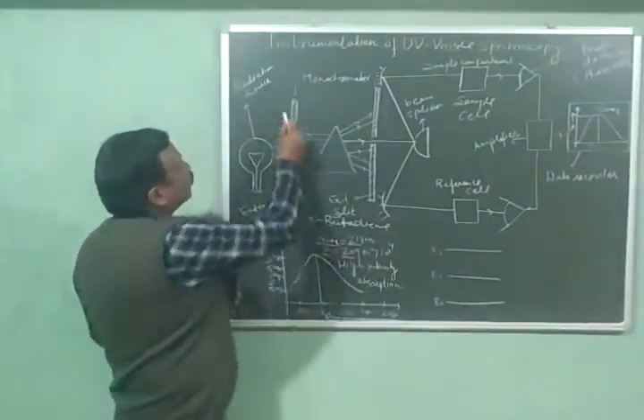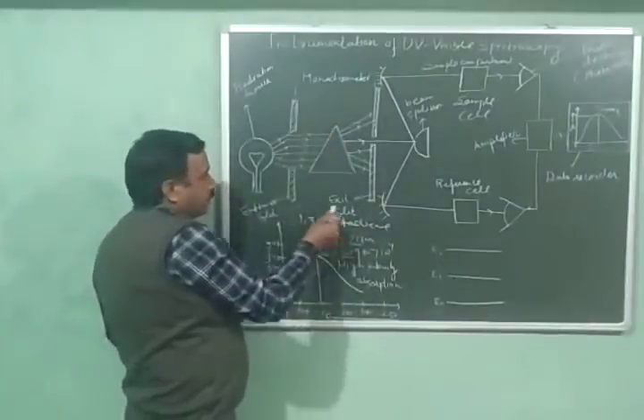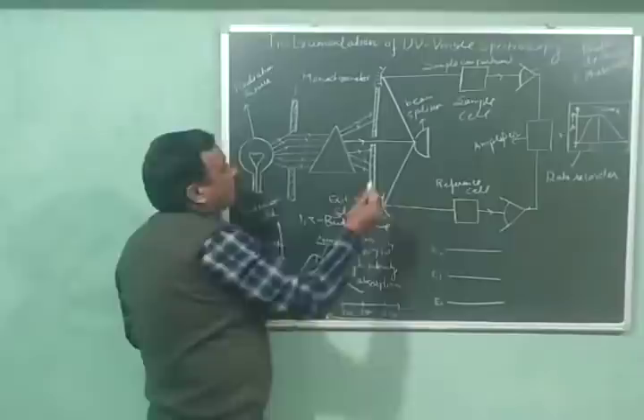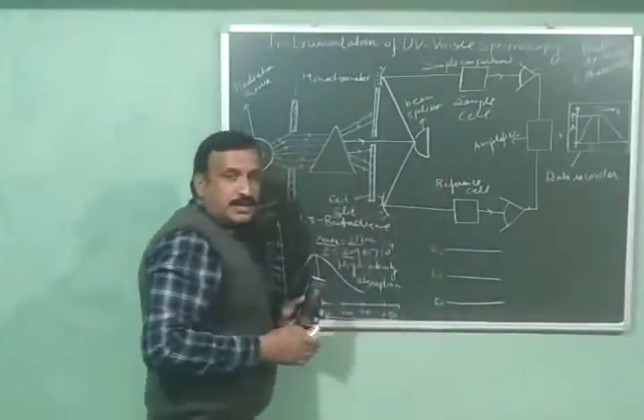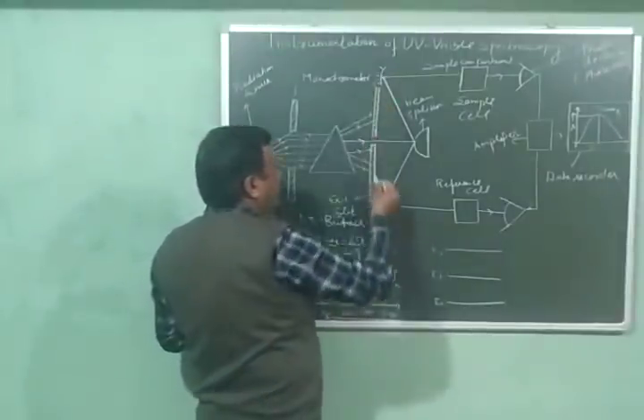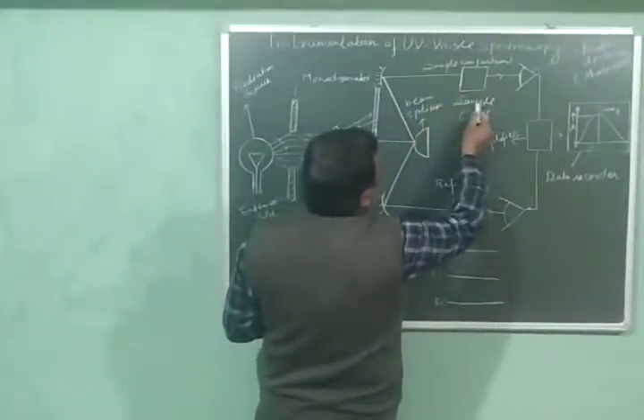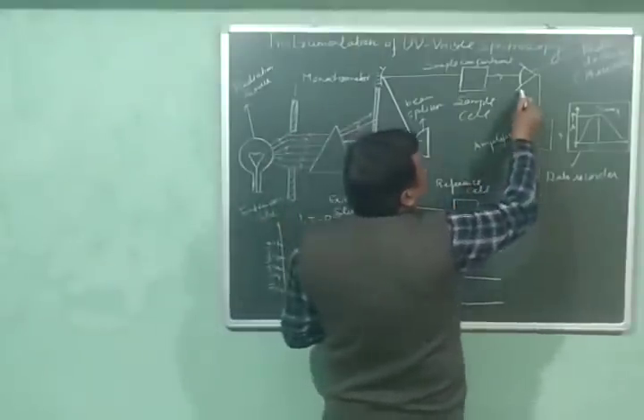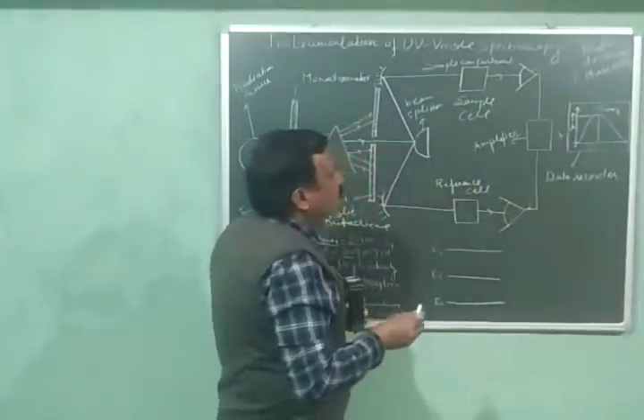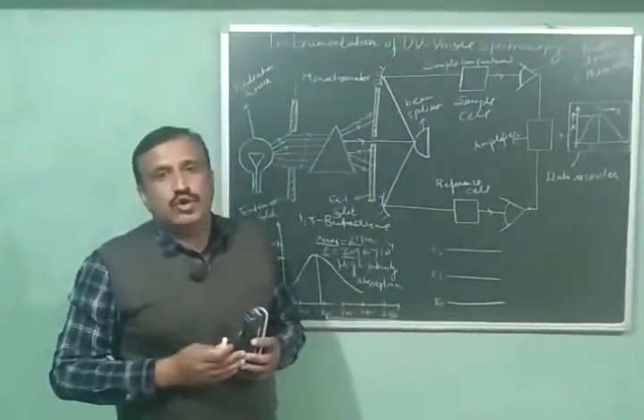The most commonly used spectrophotometers consist of a radiation source, a monochromator having two slits — an entrance slit and an exit slit — with a prism in between, a beam splitter which splits the radiation into two beams of equal intensity, mirrors to reflect the radiation, a sample compartment with a sample cell and reference cell, photo detectors with photo cells, an amplifier, and finally a data recorder.